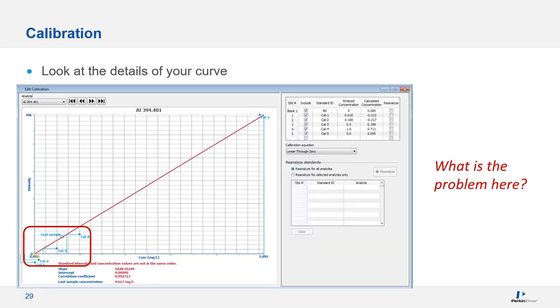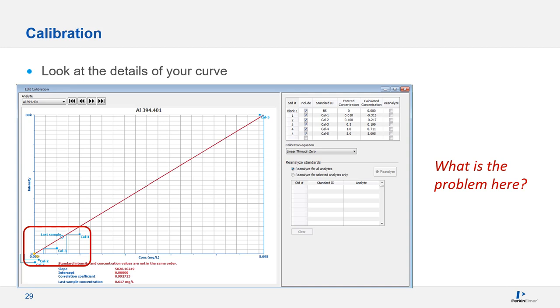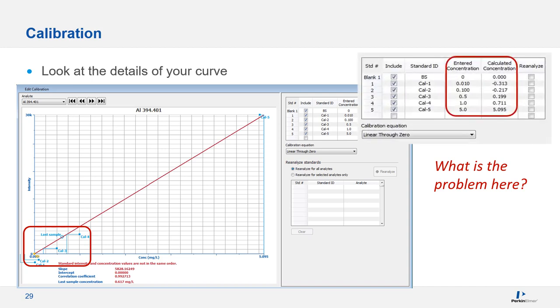In this slide, the curve type is linear through zero. The slope of this calibration curve is actually only being determined by the high calibration standard and the zero because it's being forced through the origin. The first four calibration standards are actually below the calibration line. That's because the calibration blank was contaminated and the intensity is being subtracted from all of the points, leading to a negative concentration for the first two standards. While you would get a more accurate result by not forcing the curve through zero, the real fix here is to clean up that blank contamination.